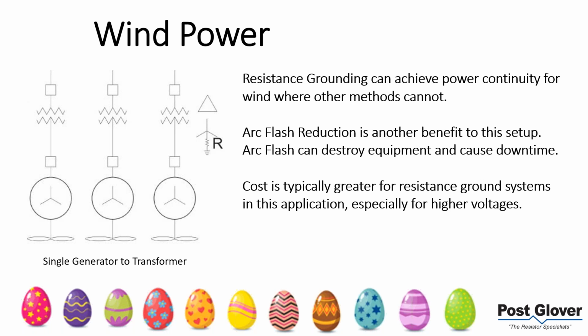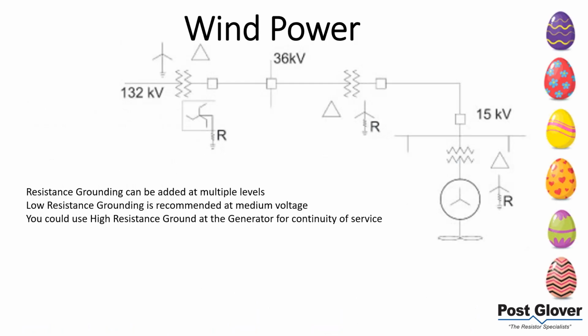So there's all kinds of different variations. You can do parallel generators, but in this application, you have a single generator transformer. You can do parallel gens to a single transformer, and there's all kinds of things you can do with this. Just an example of being able to ground at different levels. You can obviously ground your generator. You can do, for example, a high resistance ground system here.